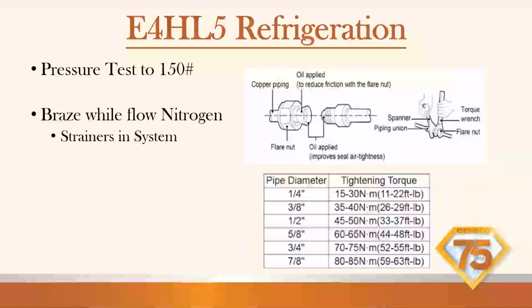I do recommend always torquing per spec. It takes out guesswork, right? I'm all about eliminating questions and concerns. If you're following the torque specs with the torque wrench, you have nothing to worry about. You're going to pressure test to 150. That is stated in the manual.